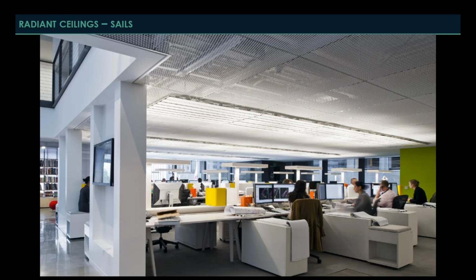It also creates a very unique architectural look to use the sail. It kind of breaks up the flatness of a normal ceiling plane and creates some architectural interest, I would say. At least I think it's interesting. Here you can see an example where chilled sails are used over the occupied portion of an open office floor plan, and the remainder of ceiling is kind of a wire mesh or metal mesh ceiling construction.